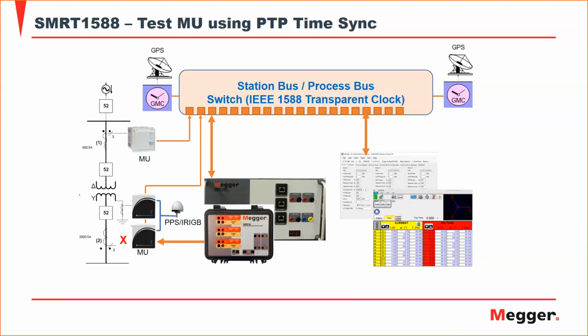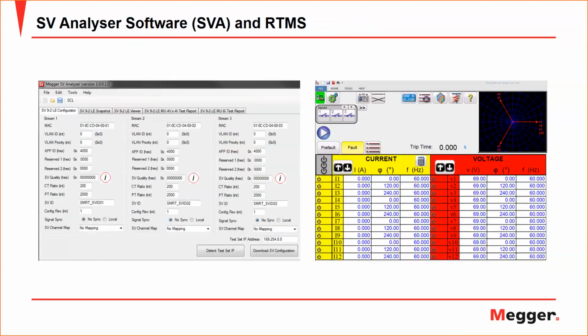And it will also be mainly controlled by similar software that we have before, the RTMS software, to use this new test equipment. But in addition to that, we have another software called SVA or SV Analyzer that will configure this test equipment. It's basically like mapping the addresses for the streams to the relays or IEDs to publish them based on our requirement from profiles, addresses, and so on and so forth. And also able to subscribe to streams that are being published by the actual merging unit in your environment. So if you are injecting real analog values in the secondary of your merging units, you can measure them as sampled values using SVA as well.